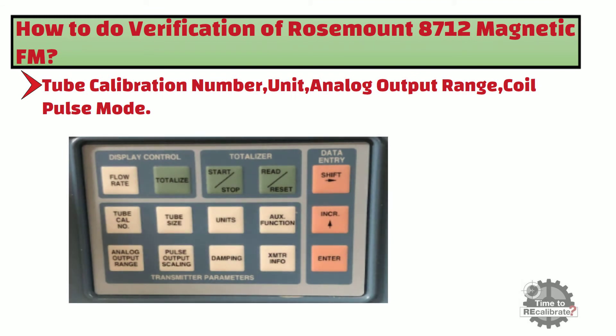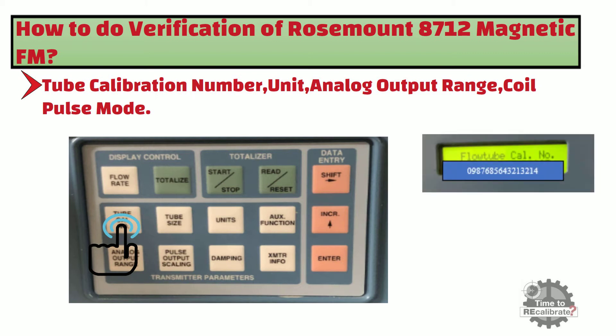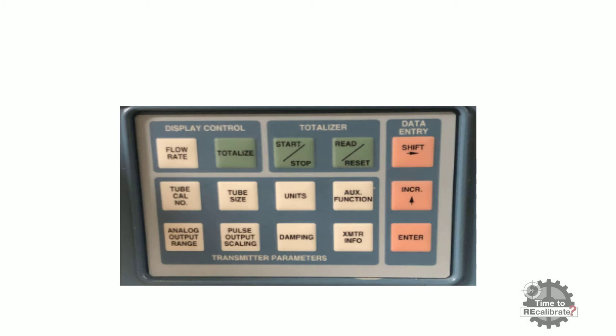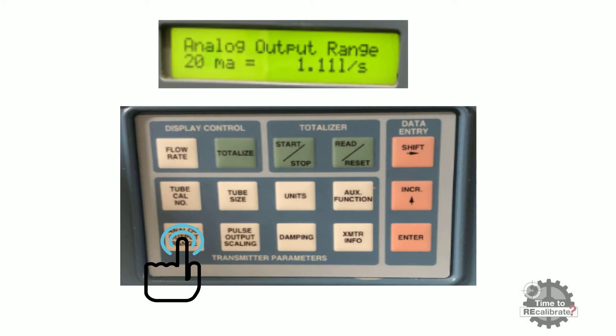In order to check the flow tube calibration number, press the tube cal number button on the local operator interface. As you can see from the picture, the 16-digit flow tube calibration number will display. Note down this value carefully. Then press the analog output range button to check the 4-20mA analog output range. As you can see from the picture, the 20mA range will display. Note down this value.